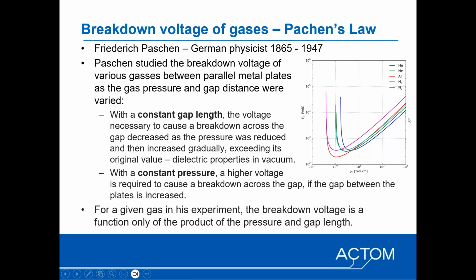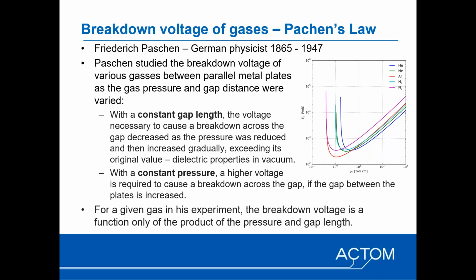So at higher pressure, typically low altitude, you'll need a high voltage, and at a high altitude, at a lower pressure, you'll have a lower breakdown voltage. But what he found is, as we approach the vacuum pressures, the availability of molecules to release electrons in the vacuum becomes less, and therefore the breakdown voltage also then increased. And that is why vacuum, in terms of vacuum interrupter, is such an ideal dielectric medium to interrupt and break current in a vacuum with very small compact distances.